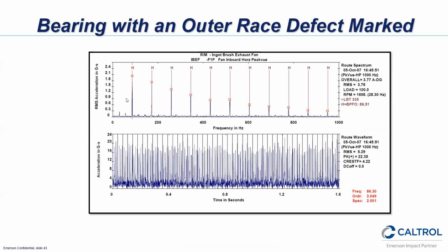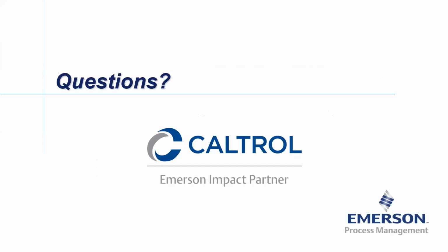Again, here's a spectrum of a bearing fault, and this bearing is programmed into the software, so we can actually see that it's the ball pass outer race frequency of that bearing showing up here with harmonics, and you see all the impacting going on in the waveform. Anything low frequency, like all the imbalance and all that stuff, is all down here. It's all filtered out. You don't see it at all. And that's about it. Open for questions.